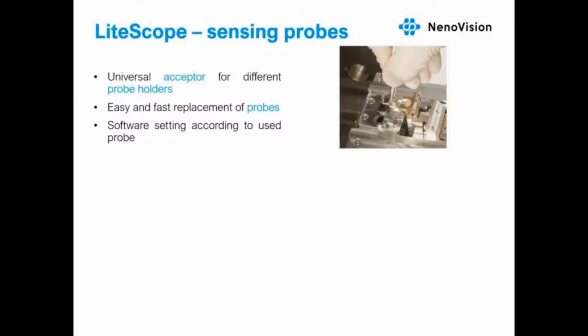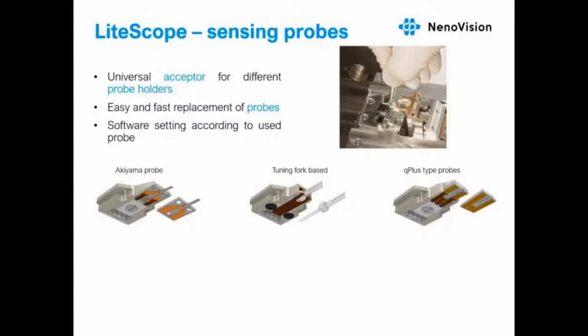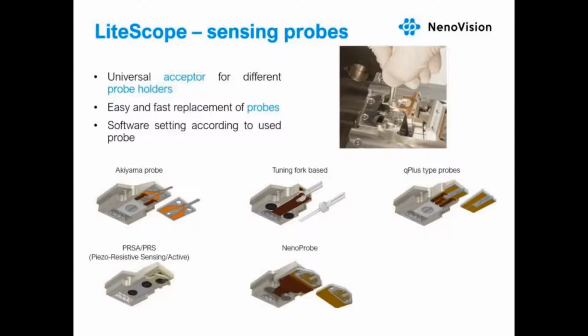So the sensing probes are crucial components of every AFM measurement, and when it comes to the AFM probes, NenoVision has chosen a different way. So instead of producing our own proprietary probes, we designed LiteScope to be fully compatible with commercially available self-sensing probes. So it contains universal acceptor for appropriate probe holders. Also, its design enables easy and fast probe replacement with pair of tweezers. Our software contains preset settings for every supported probe as well. And as for now, LiteScope supports 3 types of tuning fork-based probes, 2 types of piezo-resistive silicon probes, and also a conductive wire. And if you would like to use self-sensing probe that is not on the list, we will do our best to develop a probe holder suitable for your probe.